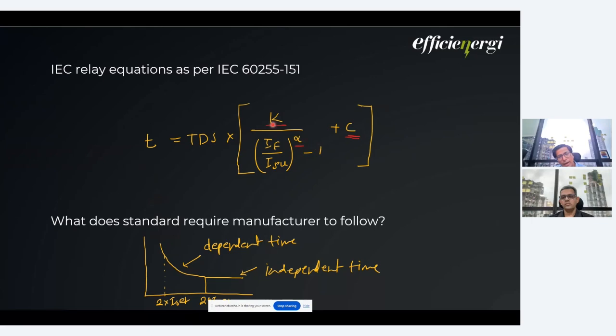So K, alpha and C are defined by the IEC for different inversities. Inversities means extremely inverse, very inverse and standard inverse. For these three inversities the values will vary, and we can have different tripping characteristics.